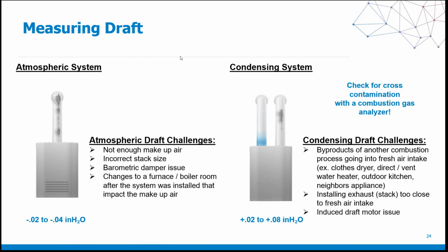When we talk about a condensing system, that obviously has its own set of challenges as well. One of the simplest things to check is, do we have an issue with our induced draft motor? The induced draft motor is integral in making sure that the byproducts of combustion leave a condensing system. And if there's an issue with that induced draft motor, that's a problem. Do we have the byproducts of another combustion process going down into our fresh air intake and impacting how the combustion is taking place and how the flue gases are leaving?